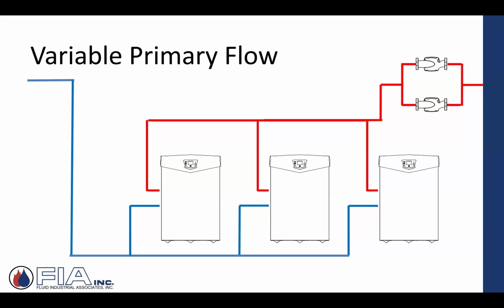Sometimes, instead of providing primary, secondary connections and primary, secondary piping, manufacturers say, hey, my boilers, it's acceptable to put them in what we would call a variable primary application, where perhaps we're using our distribution pumps to not only provide flow out to our buildings, our terminal units, fan coils, whatever the case may be, but we're also using those circulating pumps or distribution pumps to provide flow through my boiler plant in this case.